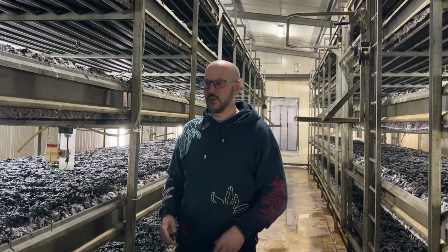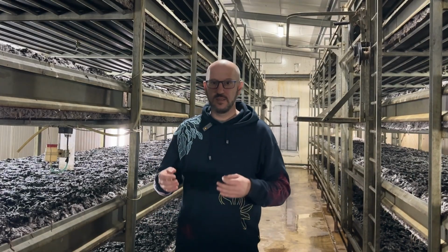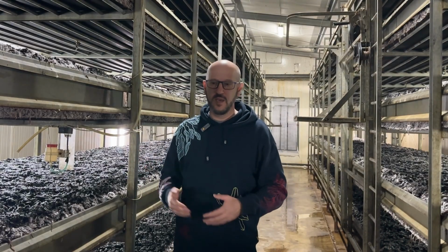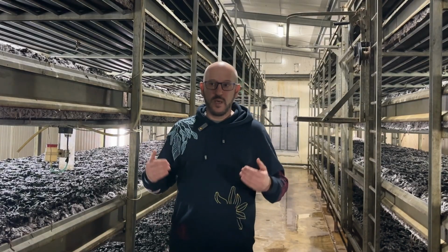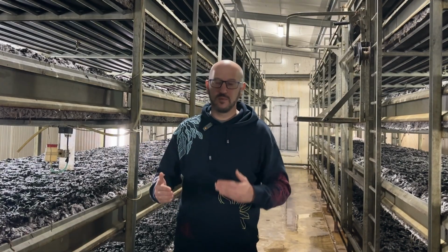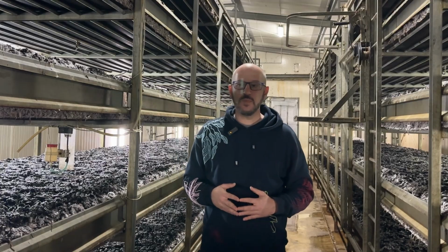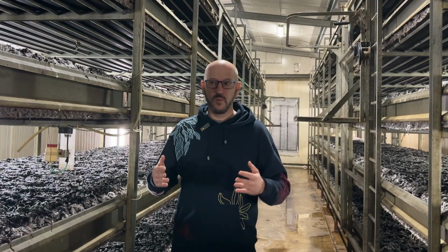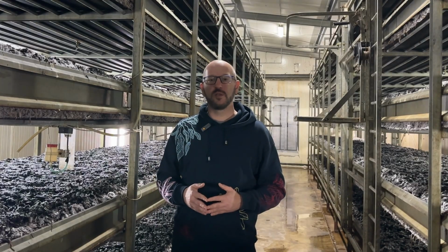The only way to manage how much CO2 we have in the room is to add oxygen, so we can add fresh air from outside. We have a fresh air damper, and when we need to make CO2 in a room lower, or to keep it as we need and not let it increase because mushrooms create it, we open the fresh air damper, which gives fresh air to the room, and we keep or lower our CO2 levels.